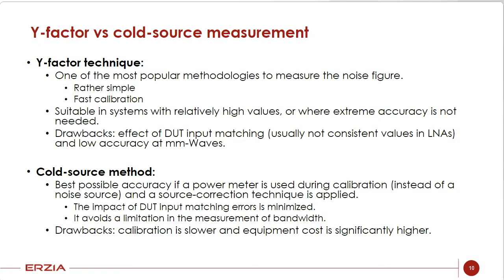The drawbacks are the input matching of the DUT, which is usually not very good for LNAs, and the low accuracy at millimeter waves. The second one is the cold source method. It provides the best possible accuracy if you use a power meter for the calibration instead of a noise source, and a source correction technique is applied. The impact of the DUT input matching error is minimized, and it avoids a limitation in the measurement of bandwidth. The bandwidth is narrower for the noise source, so it is better to use the power meter. The drawbacks are that the calibration is slower and the equipment is quite higher than using the Y factor equipment.